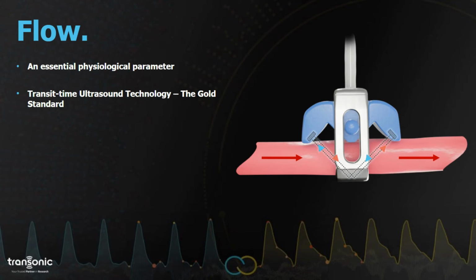Again, this was back in the 80s, and the technology was called transit time ultrasound. With this, we're able to provide absolute volumetric flow data in various different conditions. Our deployment of transit time is via a perivascular flow probe, which is a flow probe that's placed around the vessel but does not actually come in contact with said vessel. So it's a non-contact solution.